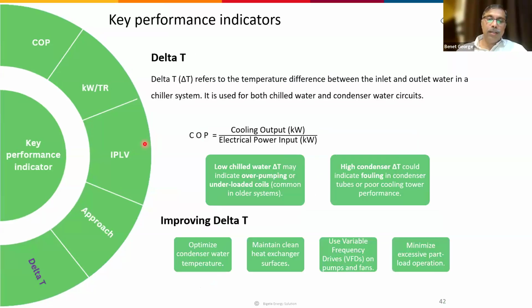Then delta T in the chilled water system. Delta T is nothing but the difference between the inlet and outlet temperature of a chiller. So low delta T is an indication that either we are supplying water higher than what is required, or the heat load is very low. Typically chillers are designed for a 5-degree delta T, and they operate highly efficiently at that delta T. So we can optimize that by controlling the water flow.